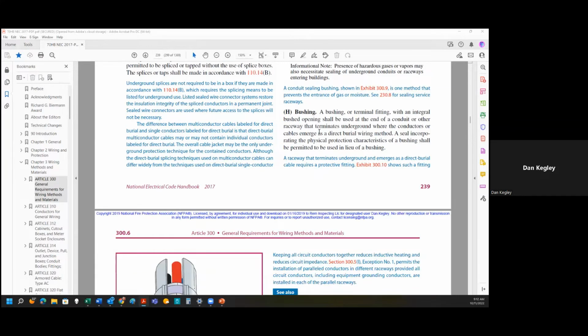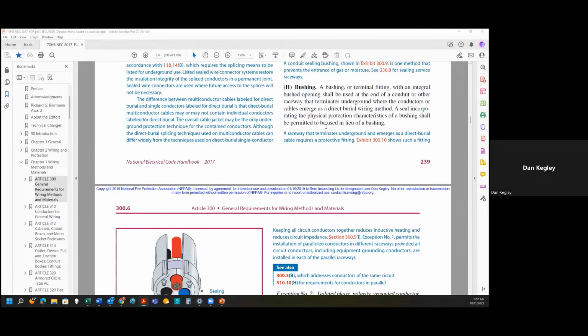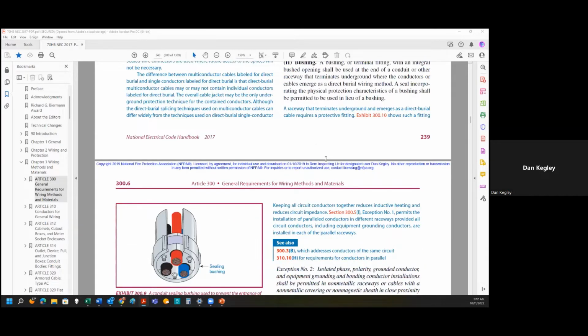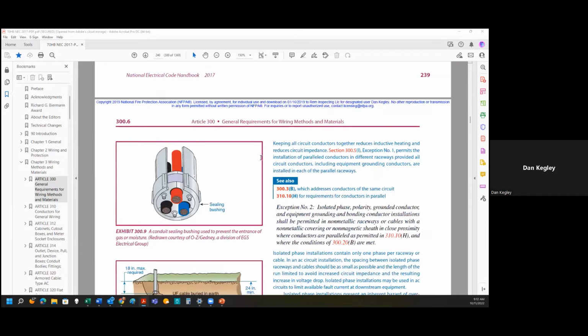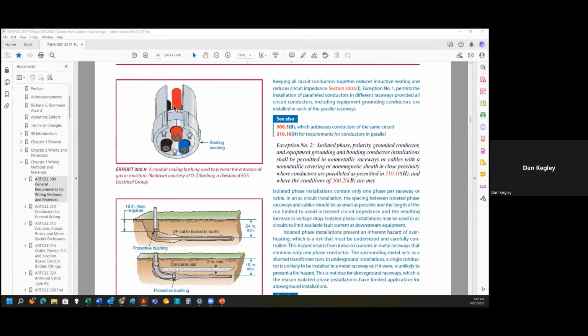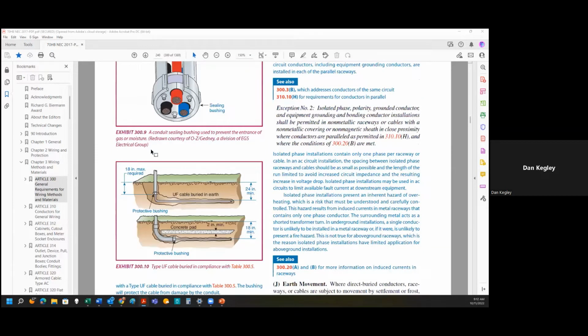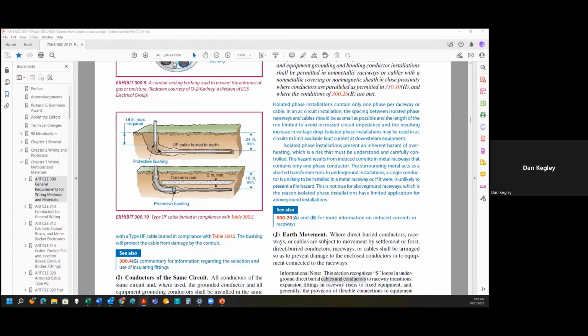There's several different styles of bushings that can be used. Lots of products out there, but basically they have a nice smooth end to it. Here's a couple pictures of a sealed bushing on the end to seal it. Is it pre-manufactured? Actually, we'll look at a Zoeller. Zoeller has a product that's very similar to this for their cords that come through. Here's a picture showing that 18 inch minimum, like in a residential scenario, and then a protective bushing on the end with that UF cable that comes in to feed that pump. So you'll have that UF cable coming in.